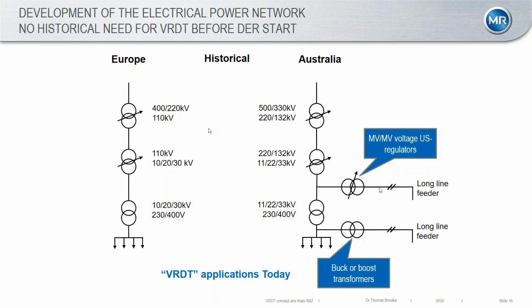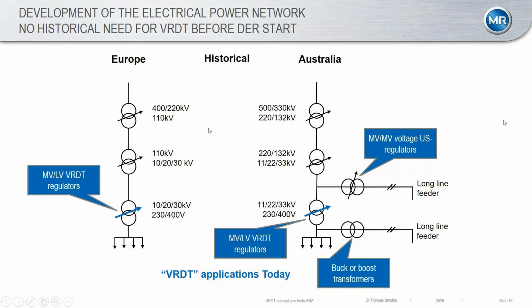Also on the LV side, sometimes there are buck or boost transformers - in Europe or Germany you'd call them farmer transformers - a fixed-step small transformer on a pole that pushes the voltage up, so that at the end of a long feeder there's still some electricity and an accurate voltage to connect and supply the customer. That's what it was like before the VRDT rollout started.